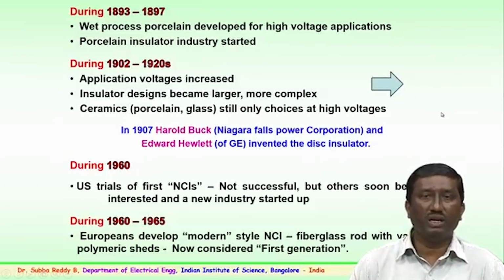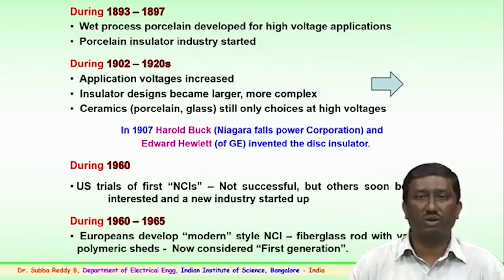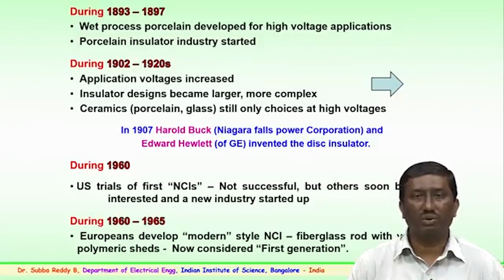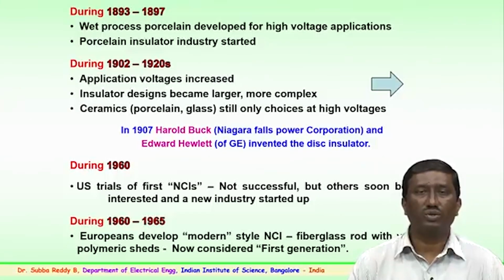So, somewhere in 1893 the wet process porcelain was developed, particularly for high voltage applications. Initially the telegraphic insulators were used up to 11 kilovolts. So, when the voltage level was increased for the transmission system, the utilities faced flashover across these telegraphic insulators. That is where the technology had to be developed, and porcelain technology was developed for high voltages. So, the porcelain industry started growing during this period for the requirement of very high voltage applications.